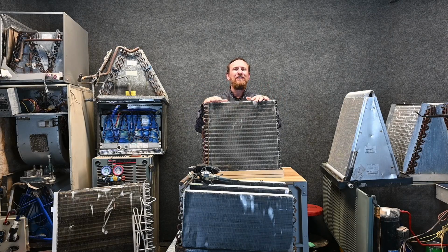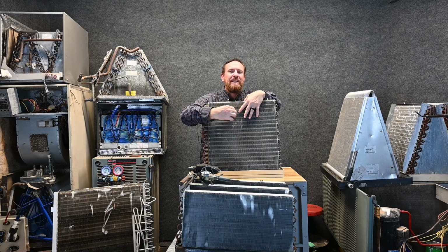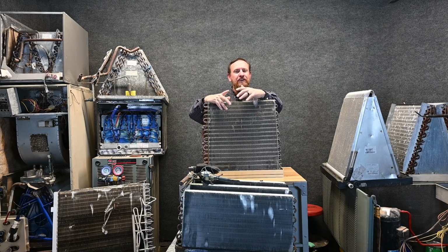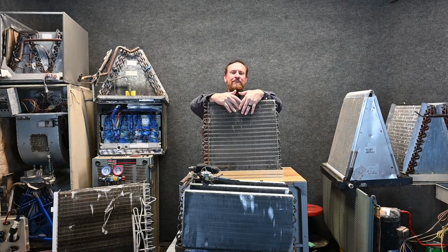Now we still have a long ways to go. We have to talk about airflow and different ways of checking airflow, but let's first start off with, is the evaporator coil going to be an airflow issue? We talked about aluminum transferring heat, but also let's think about dirt. Dirt is an insulator. So dirt does two things. Dirt blocks airflow and dirt slows heat transfer. So we don't want that.